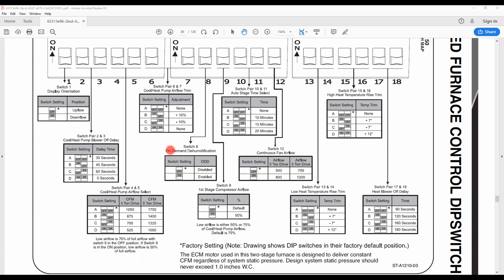All right. Moving on to switch number 6 and number 7. Now here's where it gets a little tricky for some installers and service guys. Notice switch number 6 is going to be on your first bank of dip switches. Switch number 7 is on the second bank of dip switches. So 6 will be on the far right and 7 will be on the far left. Here's your trim. So 6 and 7 work in series with 4 and 5.